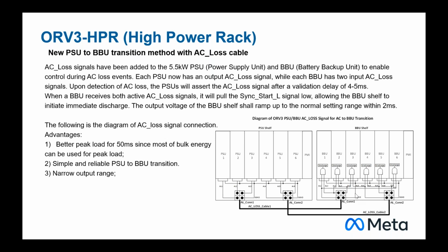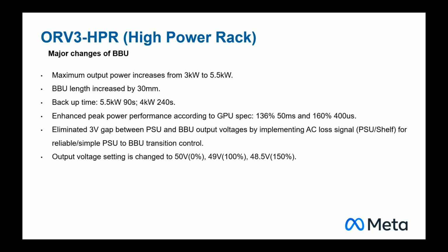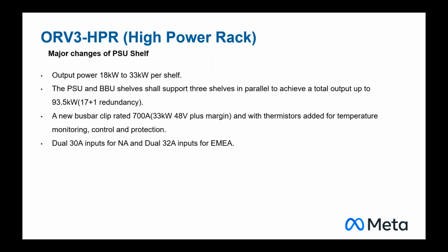David, it's Harry here. I was pleasantly surprised to see that we are approaching 100 kilowatts in the total rack power. Is that correct? In 17 plus 1? I guess this is the first I've seen. There you are, 93.5, almost 100 kilowatts. This is in air cooling. Do you believe we are reaching the limit in terms of the thermals you have seen, or what are your thoughts on that?